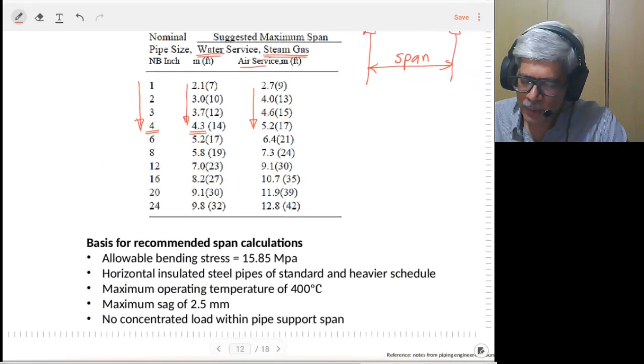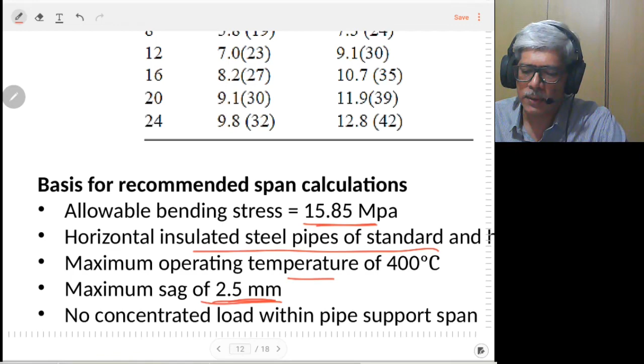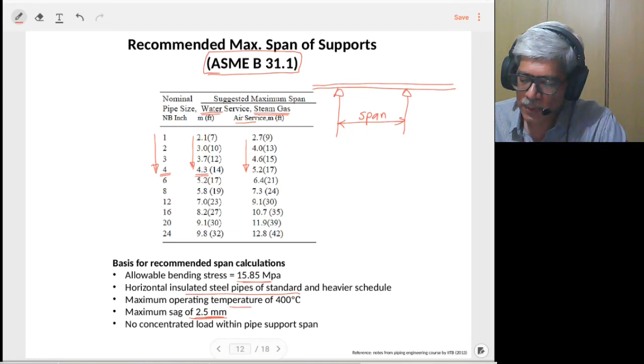It gives at the bottom what the assumptions are. Those are done for these spans. Certain allowable stress is assumed, insulation is assumed to be standard, and so on. Some maximum sag is assumed. So if your conditions are different than that, then you need to adjust these spans. As I said earlier, these are the guidelines to begin your design, and they are to be used as such for that purpose and not for finalizing the design. So this is the first guideline that we are having.